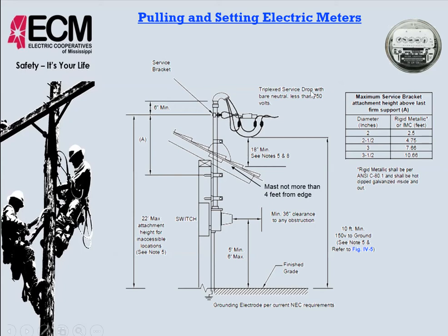Outside of a 6 foot radius from this pipe, radius would be half the distance of a circle, would need to be outside of 6 feet, would need to be 3 feet above the roof. Also here you'll notice that your service with residential pedestrian traffic only, no trucks, no horse riding, the lowest that we can be is 10 feet from the ground. That would include your drip loop as well. Okay. Another thing you need to look at is the distance of the last clamp where this pipe is secured.